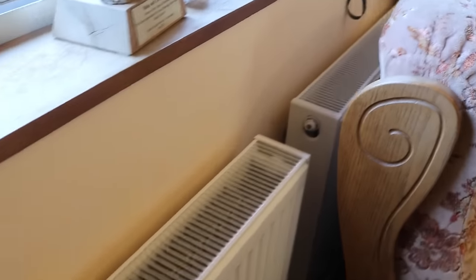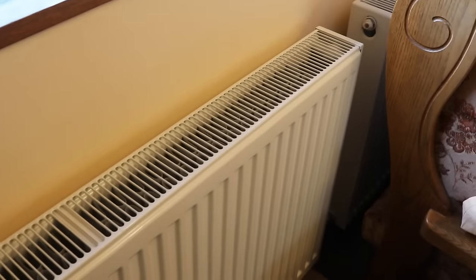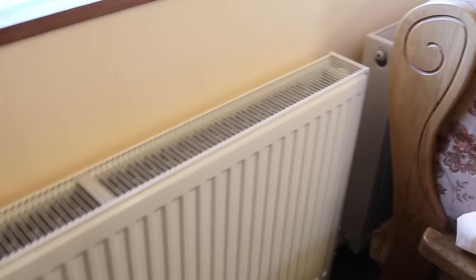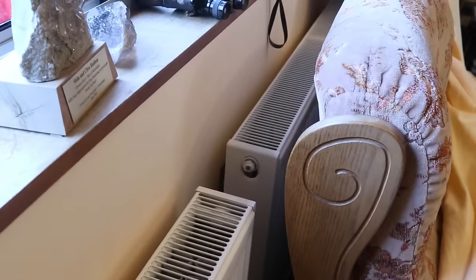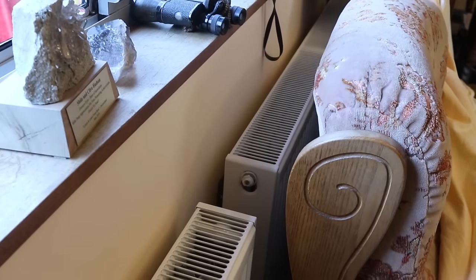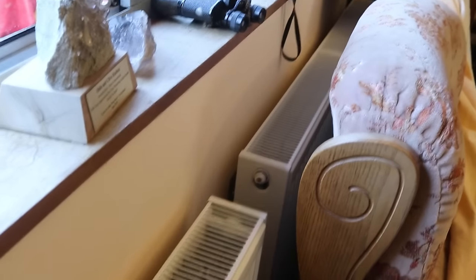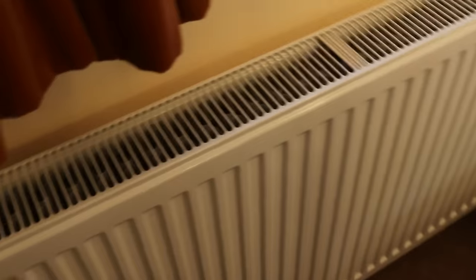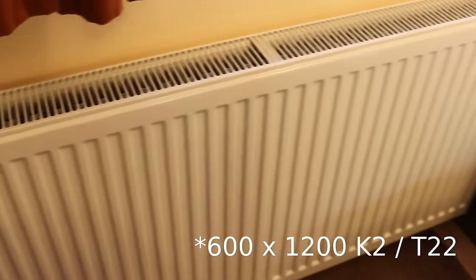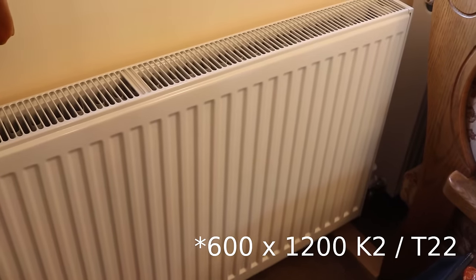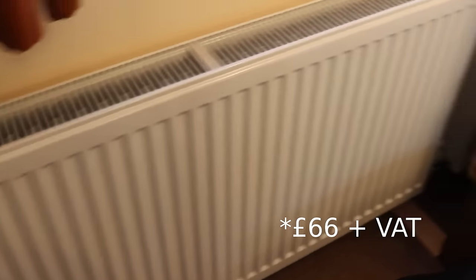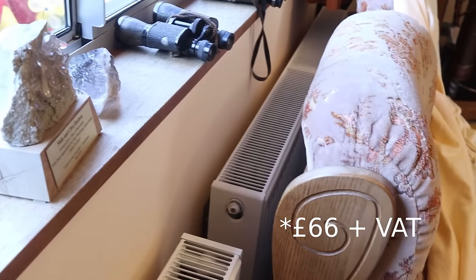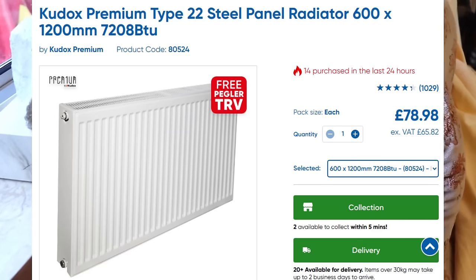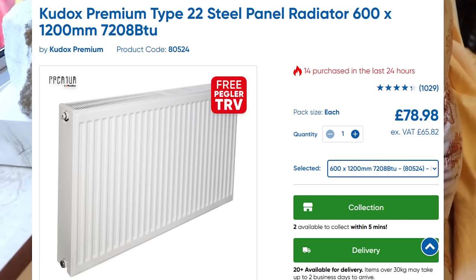So yeah, I think this is quite a useful thing that people often overlook when fitting a heat pump. You're not just limited to what radiators you have currently. If you have the space, this bit of space here wasn't being used by anything else. And the reason I fitted two radiators here, as opposed to one big one, is basically these two radiators were cheaper than one big one of this size, which would have been very big and difficult to manage. This size of radiator, it's 600 by 1200, is a bit of a sweet spot when it comes to cost. I think these are about £65 each or so, which is pretty good really for that size of radiator. If you size down, the cost increases, or if you size up, the cost increases a lot.